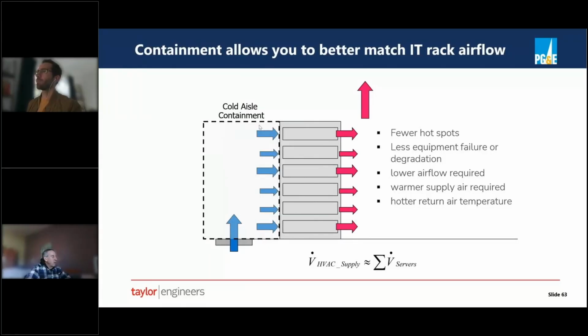Containment is basically ducting the air through the servers, right? And so one way to do that is with cold aisle containment. If you block off and duct the air on the supply side, you can basically ensure that you're getting only cold air through the servers. You'll have fewer hot spots, fewer failures. Now the supply air from your air handling system can be roughly the same as the supply volume through your servers. You can supply at a warmer temperature. You can return at a hotter temperature. That gives you lots of improvement options for energy efficiency right there.